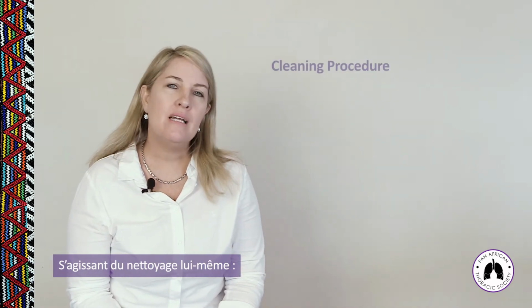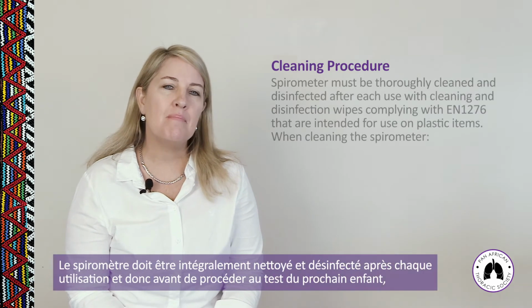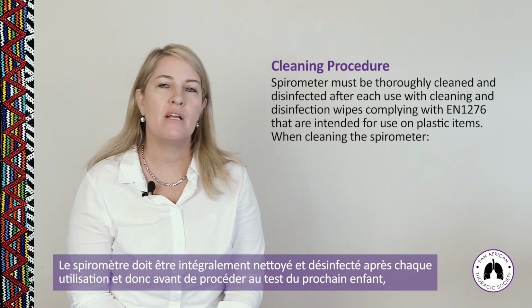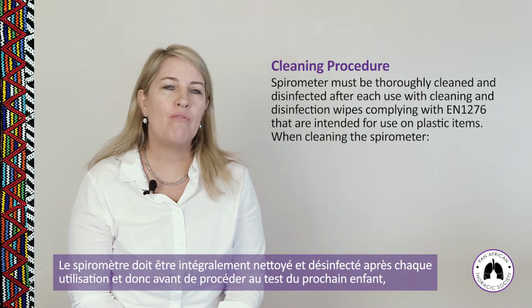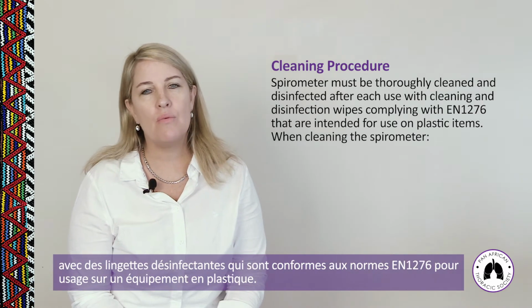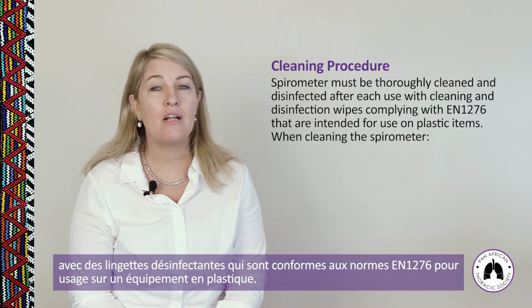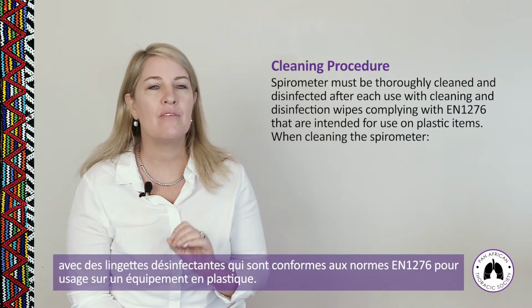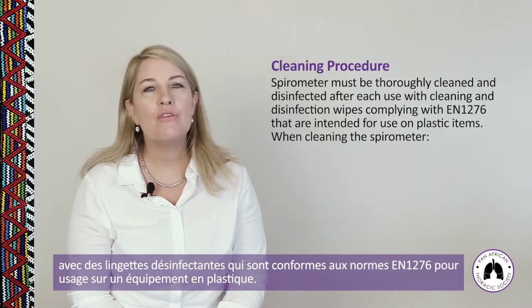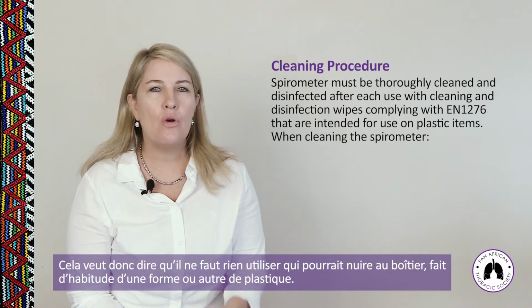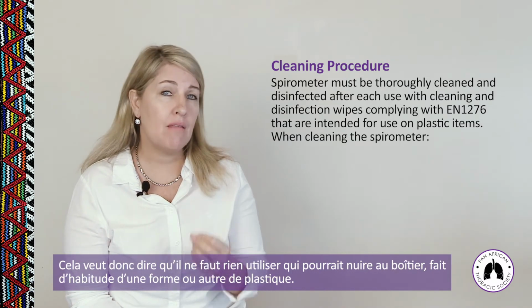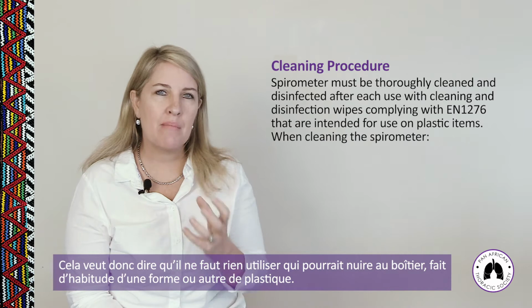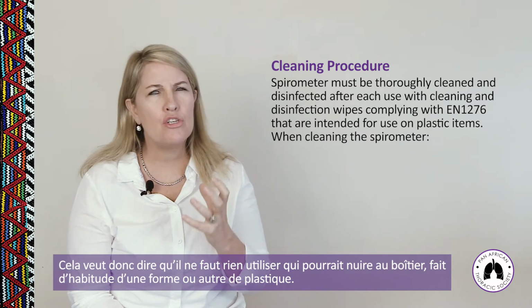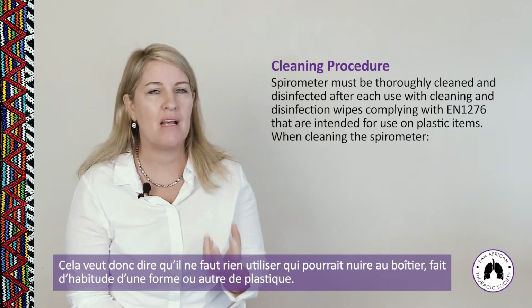The spirometer must be thoroughly cleaned and disinfected after each use, so before each new child is tested, with cleaning and disinfection wipes that comply with EN 1276, that are intended for use on plastic items. So what that is saying is don't use anything that is going to damage the casing of the spirometer, which is usually made of one or another type of plastic.